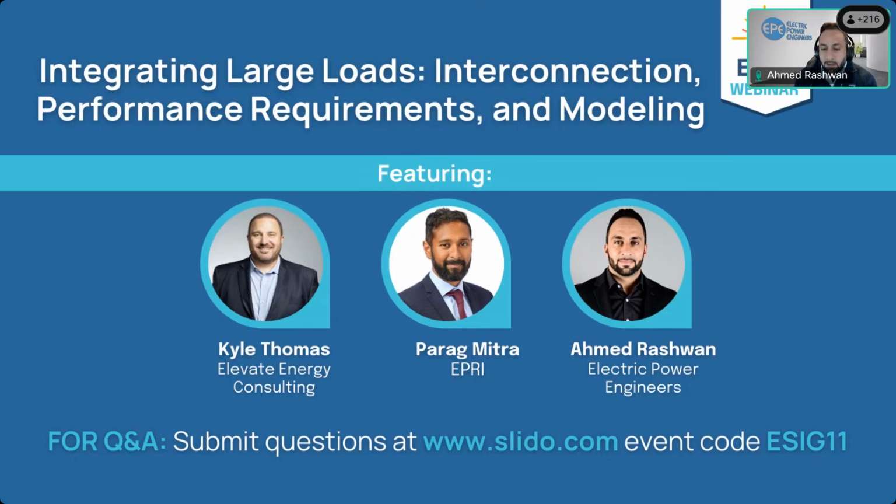approach tackling it. I think the large load community has been really forthcoming and wanting to be good citizens of the grid. And so they're looking for ways to actively ensure that they can provide the expected performance. And active power reductions during faults is one mechanism. It can also support with local voltage control as well on site. So there are different mechanisms that have been articulated, and it's really about now establishing best practices.